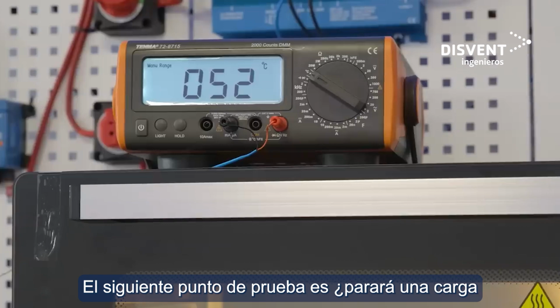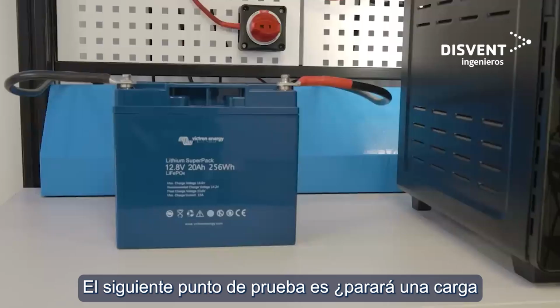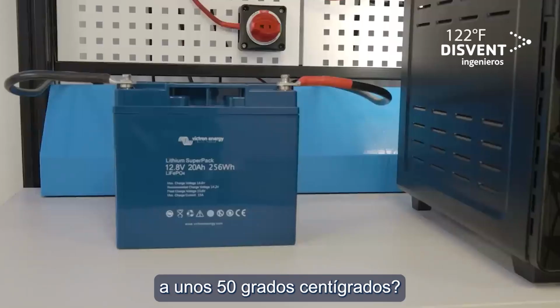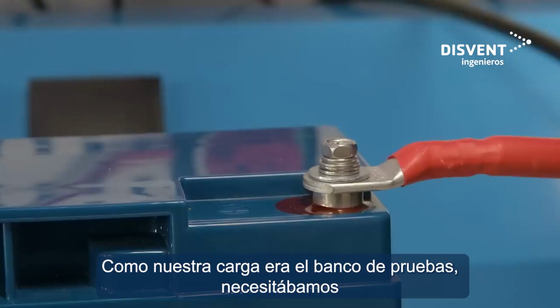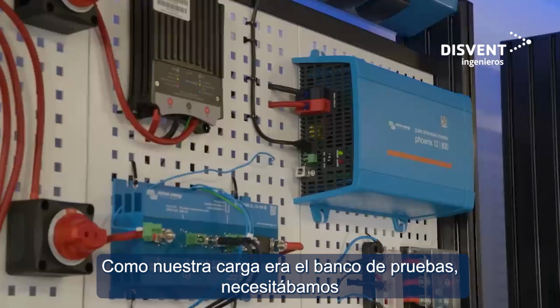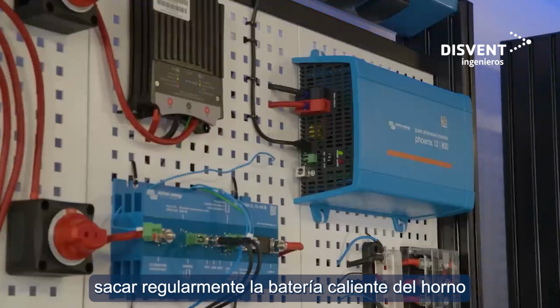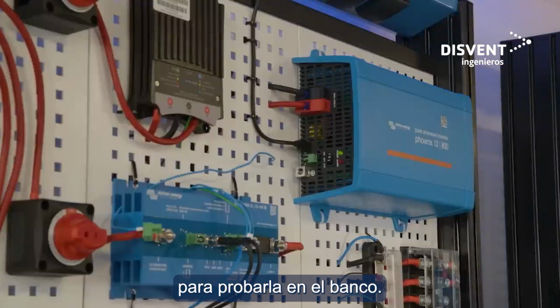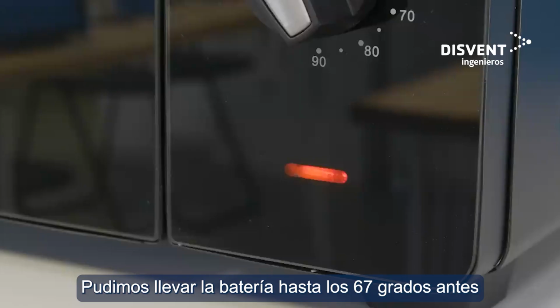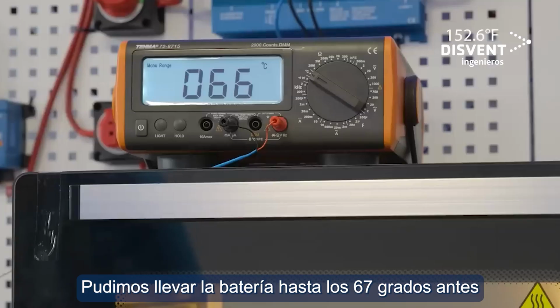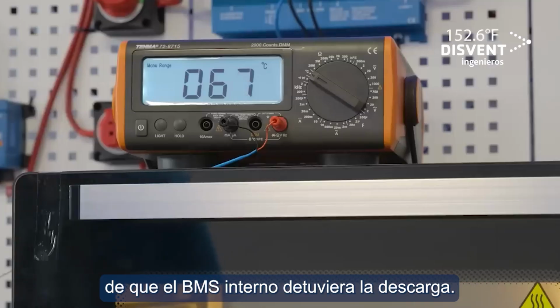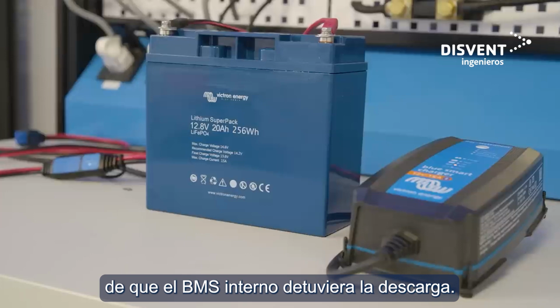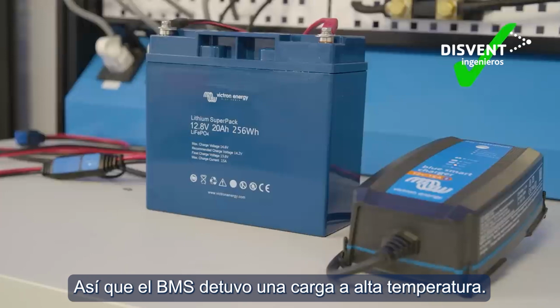The next testing point is, will it stop a load at around 50 degrees Celsius? As our load was the testing bench, we needed to regularly take the hot battery out of the oven to test it on the bench. We were able to take the battery up to 67 degrees before the internal BMS stopped the discharge. So the BMS has stopped a load at high temperature.